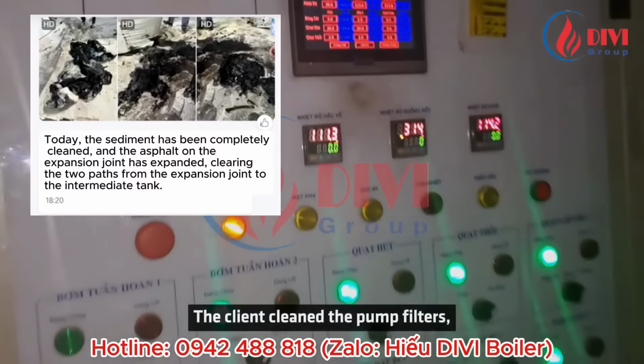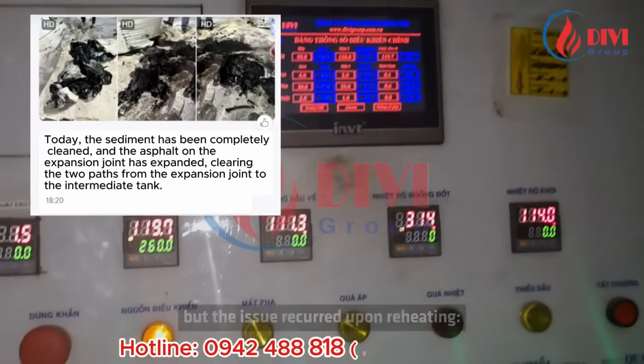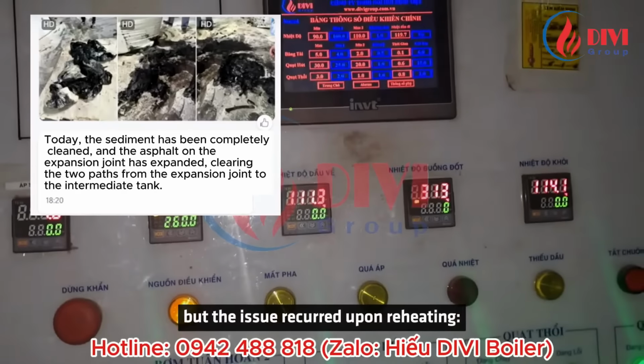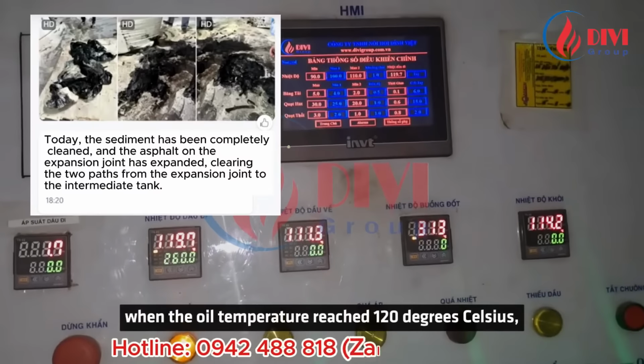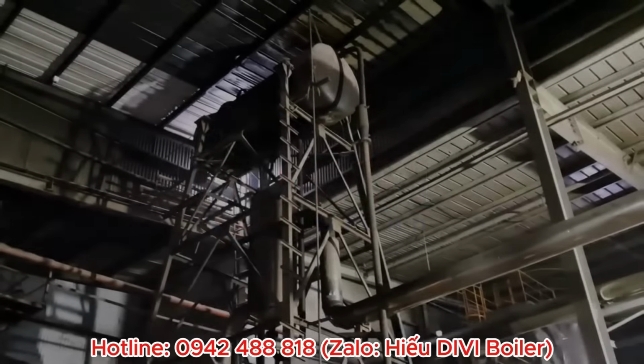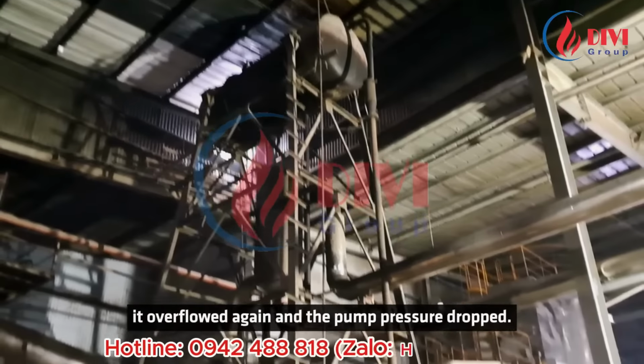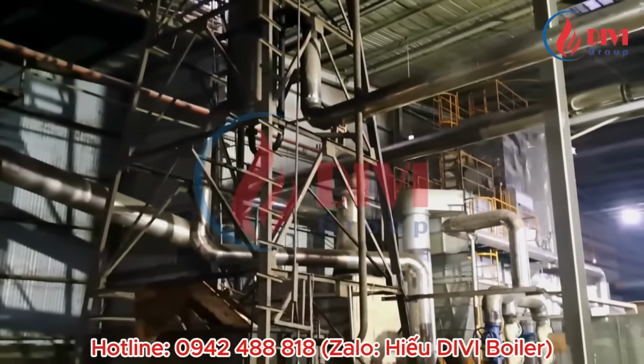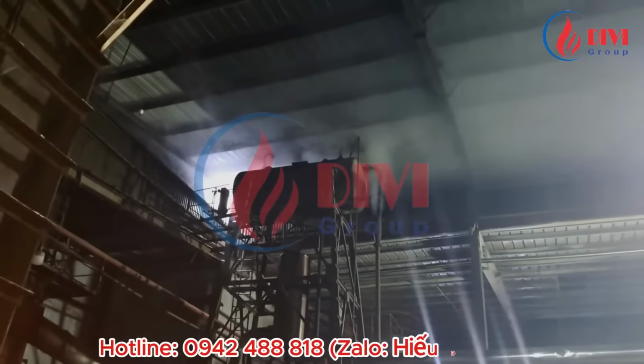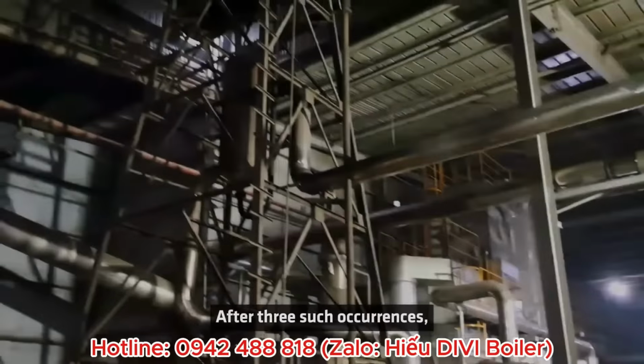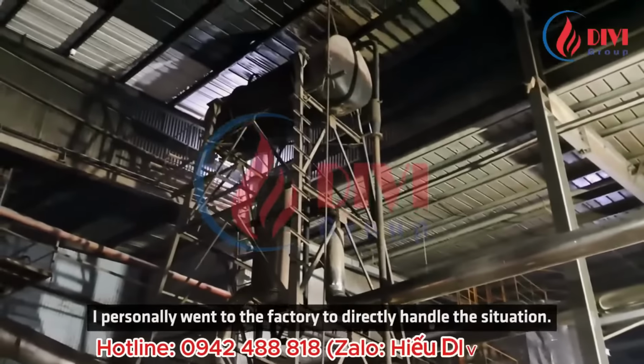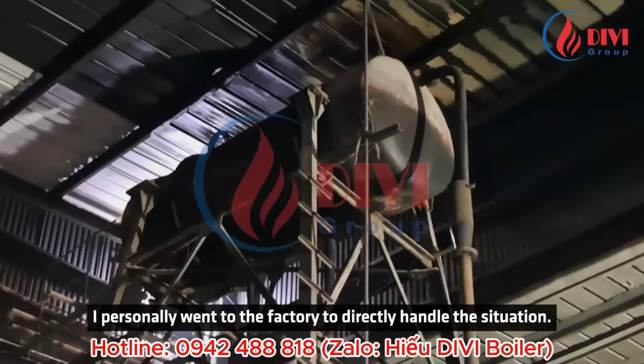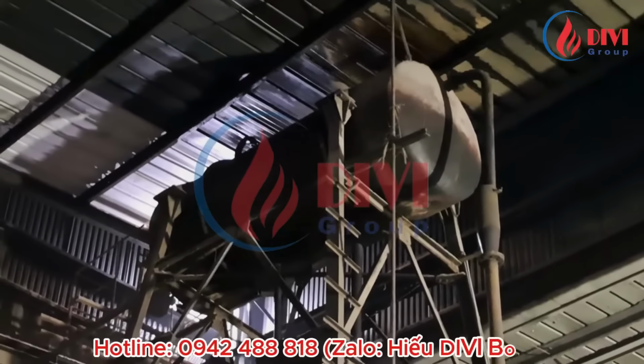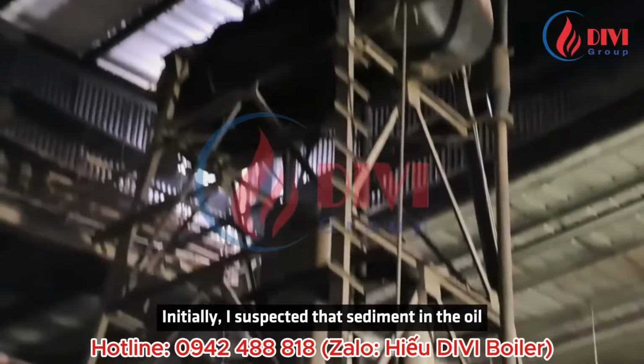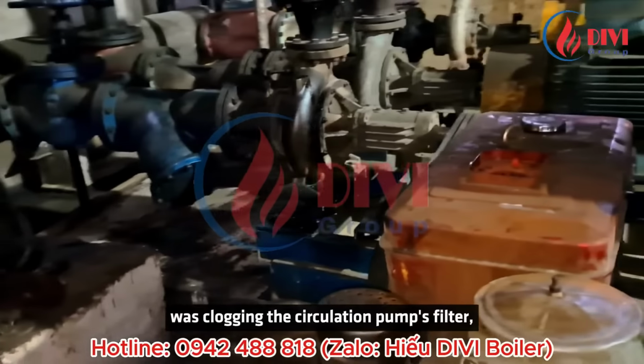The client cleaned the pump filters, but the issue recurred upon reheating when the oil temperature reached 120 degrees Celsius. It overflowed again and the pump pressure dropped. After 3 such occurrences, I personally went to the factory to directly handle the situation. Initially, I suspected that sediment in the oil was clogging the circulation pump's filter.